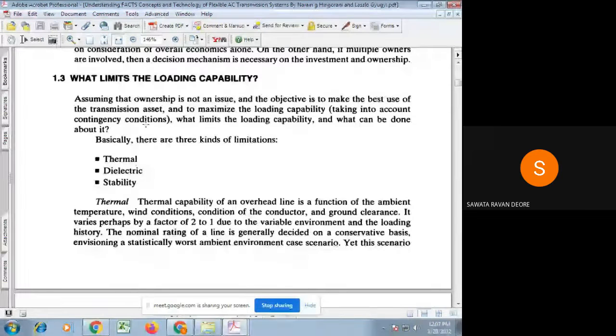If we consider one particular transmission line, then the power handling capacity of that transmission line is what helps us to load that transmission line according to system requirement. So the factors which limit the power handling capacity of the transmission lines are thermal rating, dielectric rating, and stability limitations.